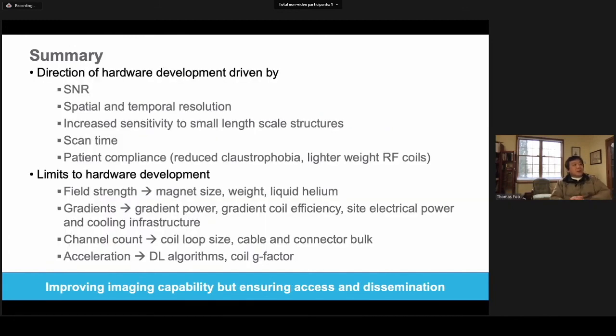So in summary, the direction on hardware development is driven by imaging requirements of SNR, spatial and temporal resolution, and needed sensitivity to small length scale structures. All of this needs to be achieved in short scan times where patient compliance is critical. Now, in terms of hardware development, there are limits. Field strength, for example: magnet size, weight, and helium volume limit how high field strength can go, including the magnet superconductor.